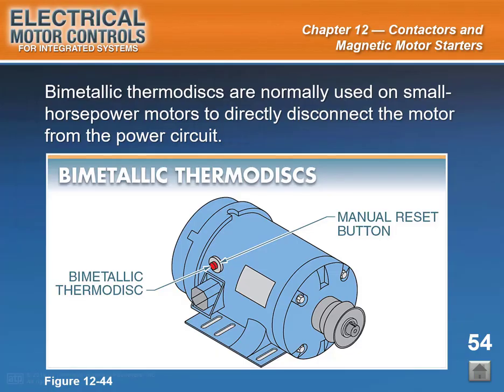A bimetallic thermodisc operates on the same principle as a bimetallic strip. The differences between these devices are the shapes of the devices and their locations. A thermodisc has the shape of a miniature dinner plate and is located within the frame of a motor. A bimetallic thermodisc warps and opens the circuit when a motor is overloaded.